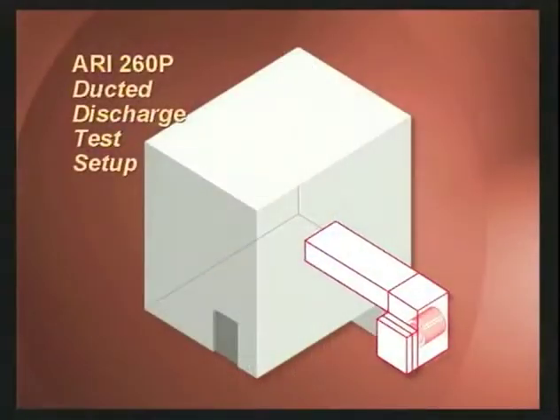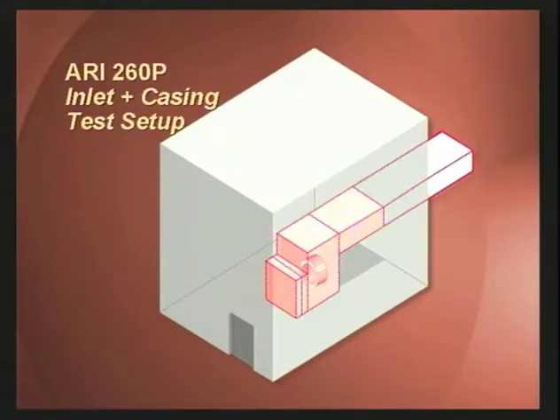The first one, as I mentioned before, is the ducted discharge. In this case, we have a setup of a reverberant room and the product, which is outside the room. However, as you can see, there's a duct from the product where we duct the discharge into the reverberant room for measuring the discharge sound. In the second test setup, we're taking a look at the inlet plus casing sound. In this case, we actually put the product within the reverberant room. However, we duct the discharge out. And this way, we're able to measure both the inlet plus the casing radiated noise.